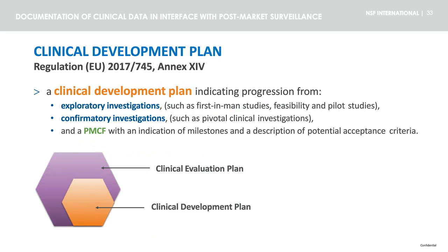A clinical development plan should indicate the progression from exploratory investigations such as first-in-man studies, feasibility and pilot studies, to confirmatory investigations such as pivotal clinical investigations, and planned PMCF activities with the indication of milestones and potential acceptance criteria.